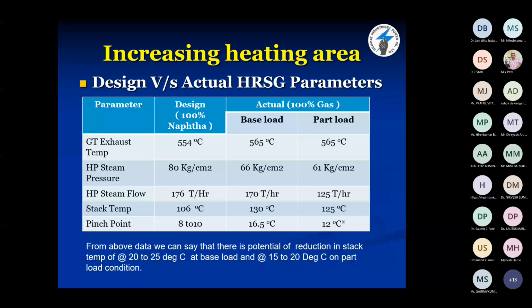What is the pinch point and approach point, I think all of you might be knowing. So I cannot go into the depth of the pinch point and approach point, but I can just say that the pinch point was designed for 8 to 10 degree, and in actual condition it was coming from 16.5 to 12 degree, and the major loss was of the stack temperature. So you can see from the above data that there is the potential of reduction in stack temperature of 20 to 25 degree at base load and 15 to 20 degree on part load condition.